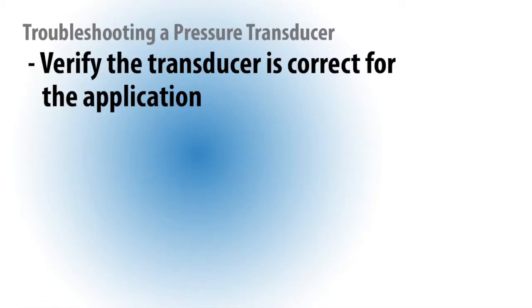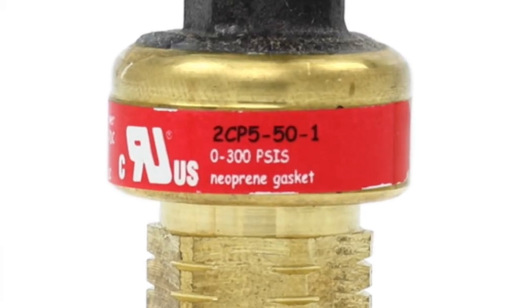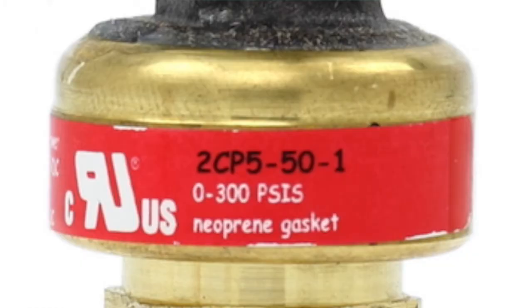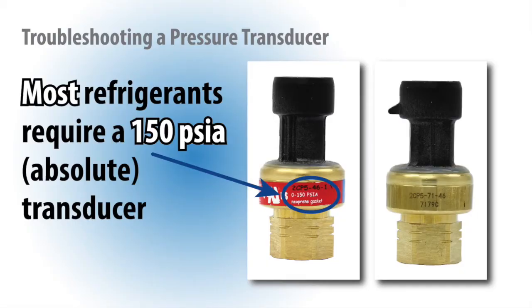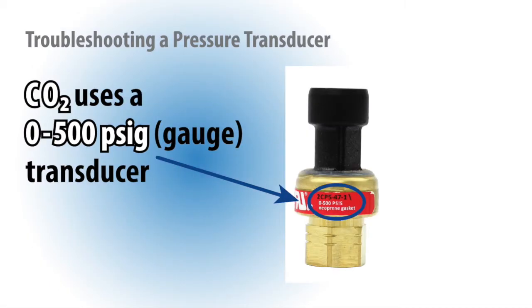To ensure the pressure transducer is reading correctly, first verify the pressure transducer is correct for the application. The model number, as well as range, should be marked on the unit. For most refrigerants, the controllers use a 0 to 150 psia or absolute transducer. For R410A, the controllers use a 0 to 300 psig or gauge transducer. And finally, CO2 uses a 0 to 500 psig or gauge pressure transducer.